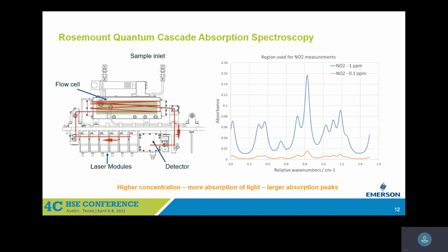So how does it work? What you see on the left-hand side is a cross-section of our optical bench. And right here are the laser modules. Then you've got your flow cell with mirrors on either end. And we direct the laser light. There's up to 6 laser modules going into a Herriott cell, an astigmatic Herriott cell. Your sample comes in and out, and the light bounces back and forth over a particular optical path length. The longer the optical path length, the more sensitive the measurement. So we have a variety of different path lengths.